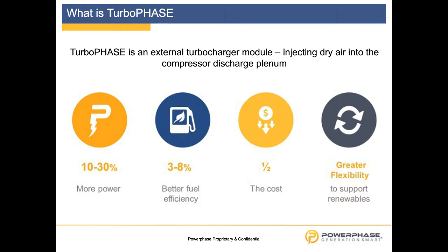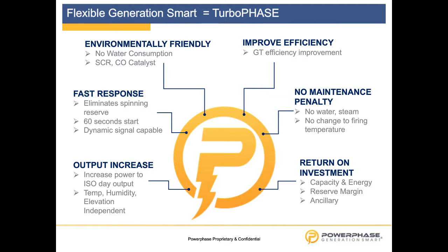The key benefits in more detail are the output increase, as just mentioned. As a ballpark, we bring the output back to the ISO condition of the gas turbine, independent of humidity, temperature, or elevation. We are a fast response. We can inject dry air within 60 seconds from the demand signal. That means we are a fast response, and in some markets we represent spinning reserve. We are environmentally friendly. There is no water consumption in our system, neither for the operation of our system nor for the augmentation or enhancement of the gas turbine.